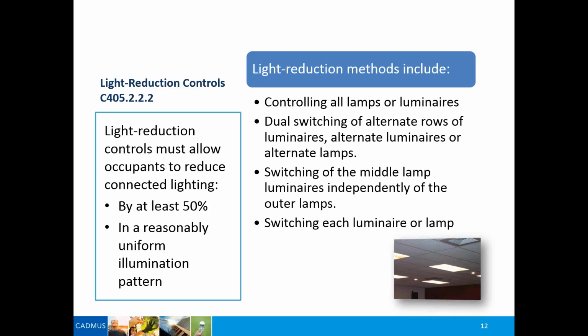And so the requirement has not changed based on what you currently have in the 2006 code. The requirement is still to reduce the lighting level in a reasonably uniform illumination pattern, which is essentially you don't want half the room light, half the room dark. If I've got 2x4 fixtures in the ceiling, say 3-lamp fixtures, I could control the center bulb on each one of those fixtures on one control, and I could control the outboard bulbs on another control. So I can either reduce the lighting level in that space by 33% by switching all the interior bulbs off, or by 66% by switching the outer bulbs off, and that satisfies the requirement to be able to reduce the lighting load by at least 50%.